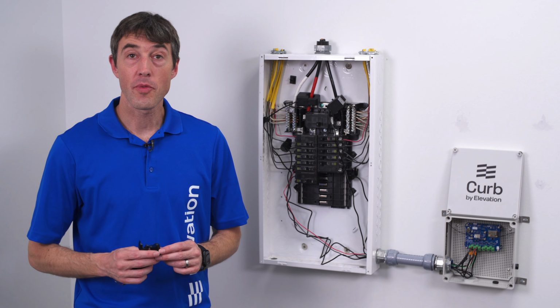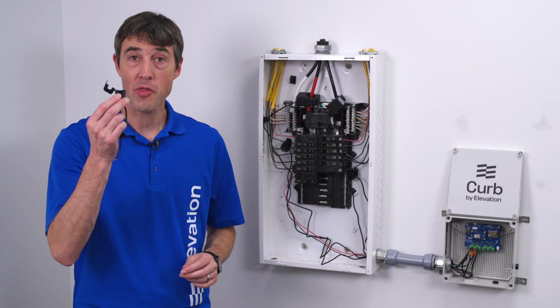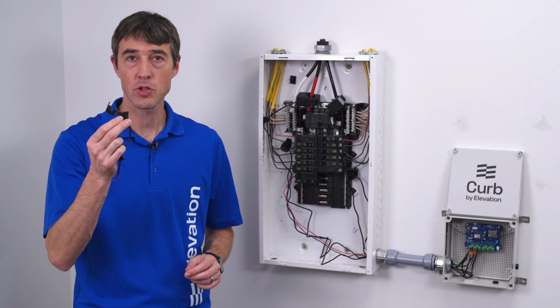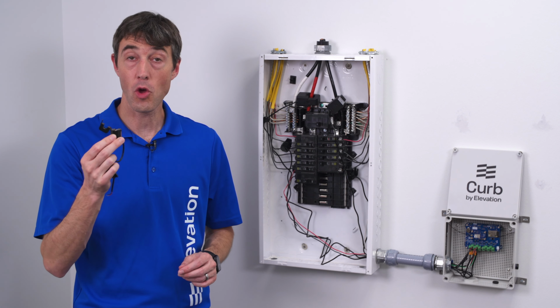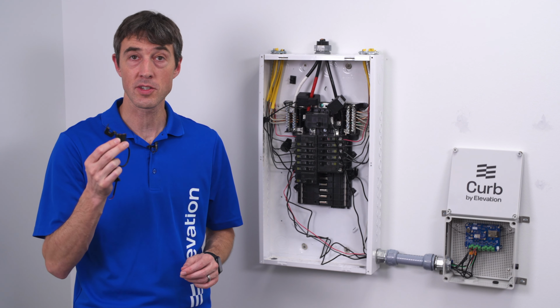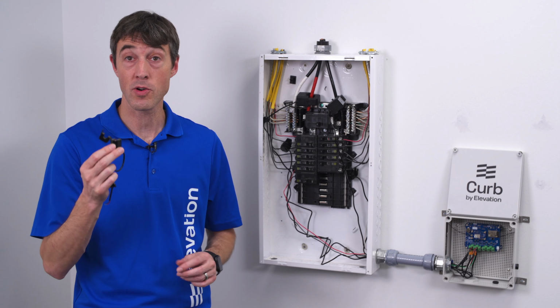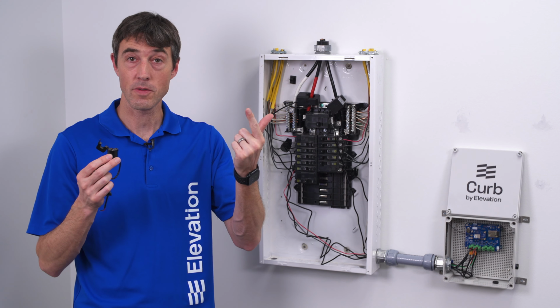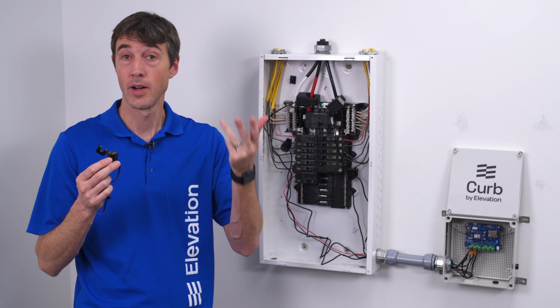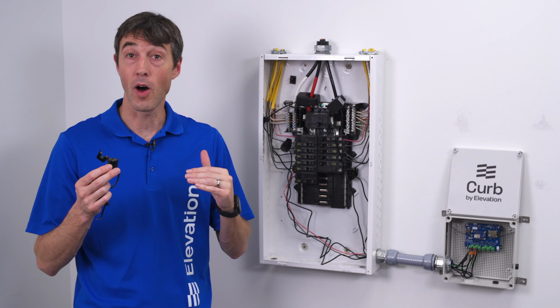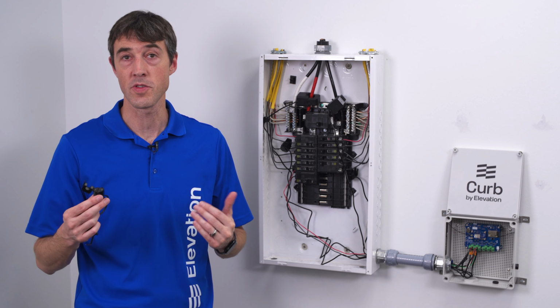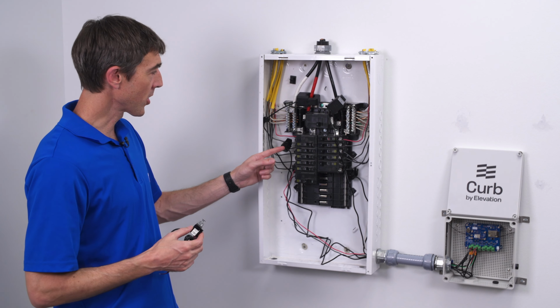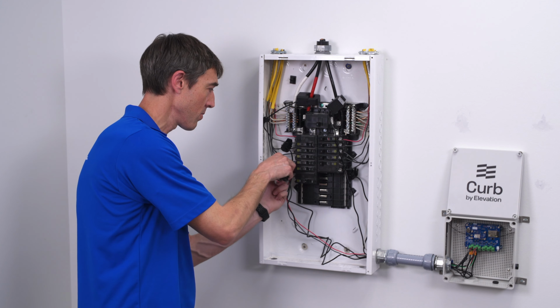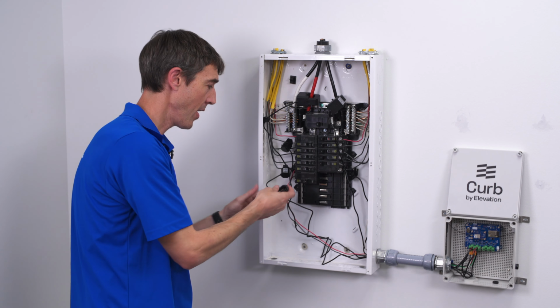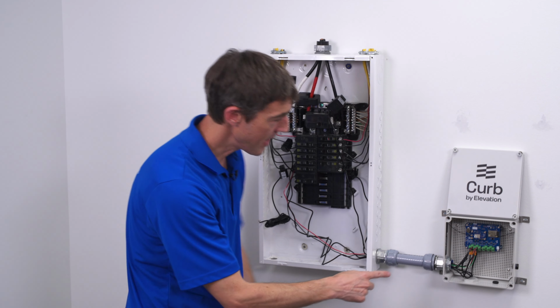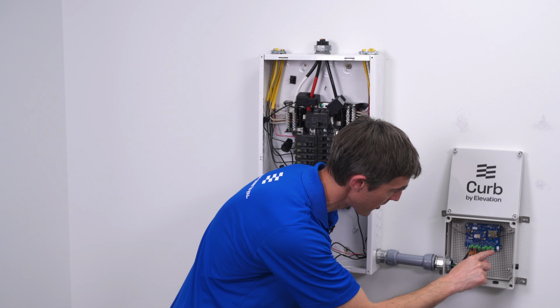You're going to want to install the other 8 CT clamps, the small 30 amp CT clamps, on the electrical panel branch circuits. You should follow our priority list of circuits to monitor. Typically, the highest priority is solar, an air conditioner, an air handler, a pool pump, or an electric vehicle. There are a handful of other priority circuits that you can reference later in this video. The way that you're going to install that is simply snap the sensor around the individual branch circuit and run the wire through the conduit and into the individual ports on the Curb device at the top here.